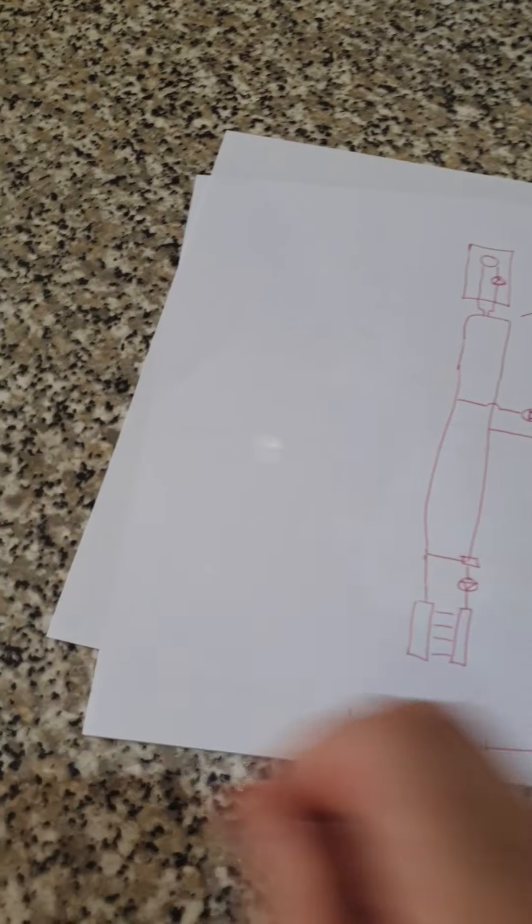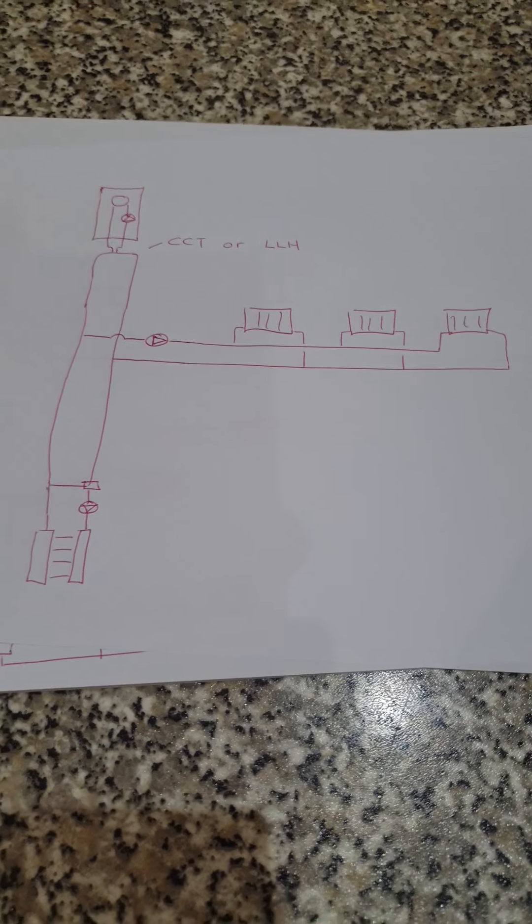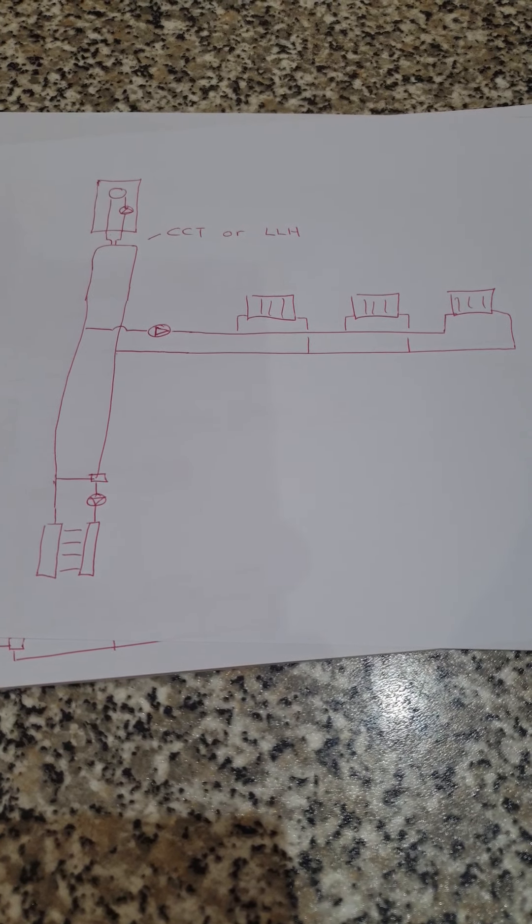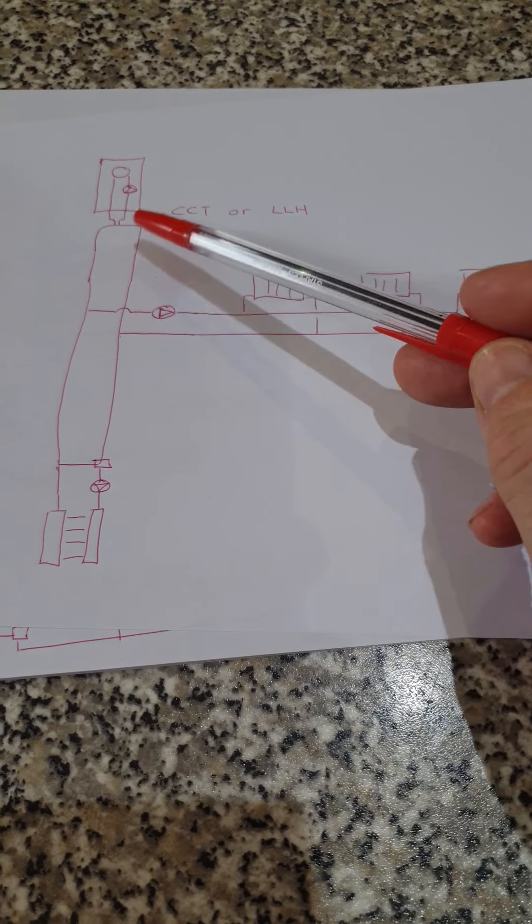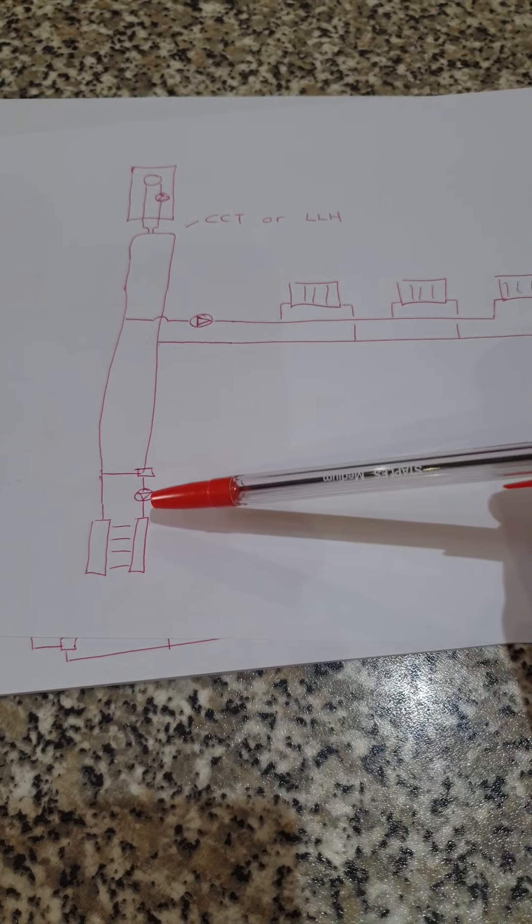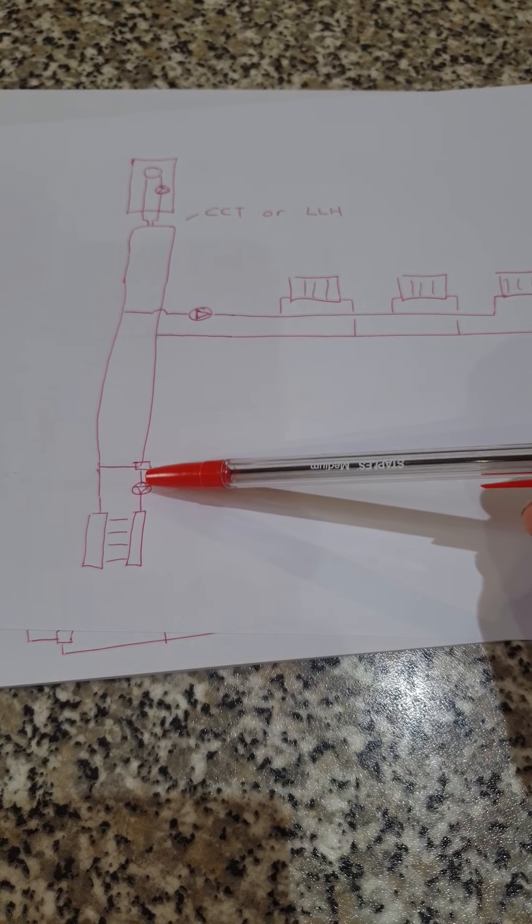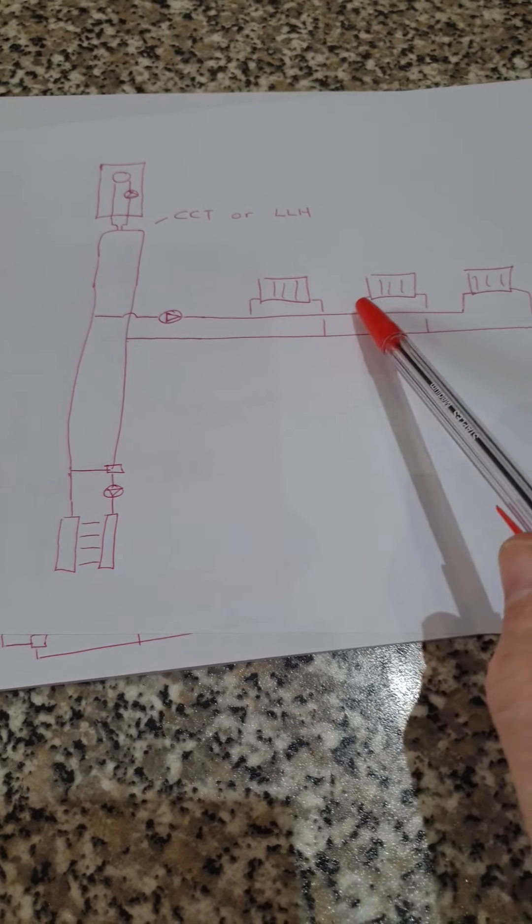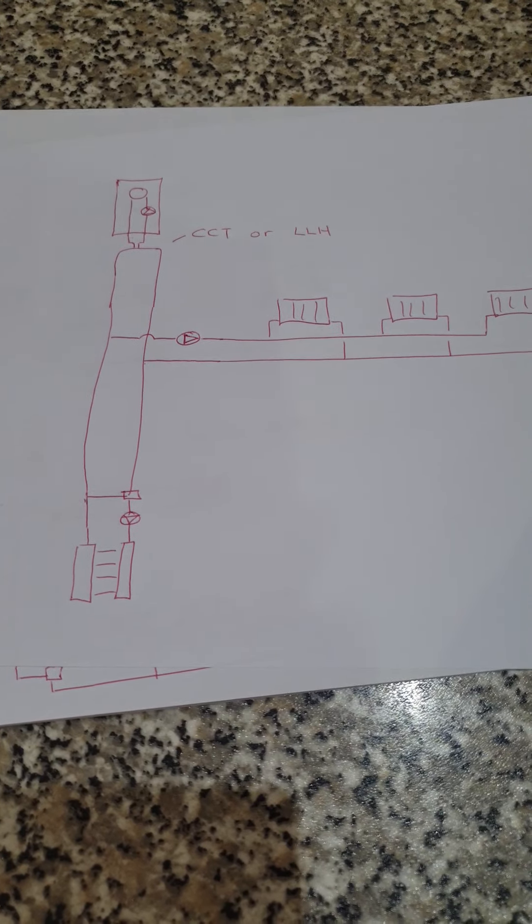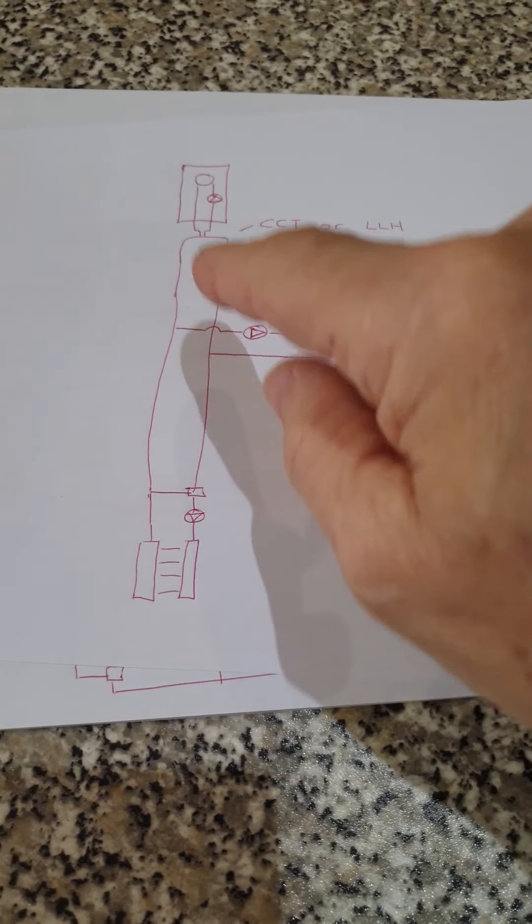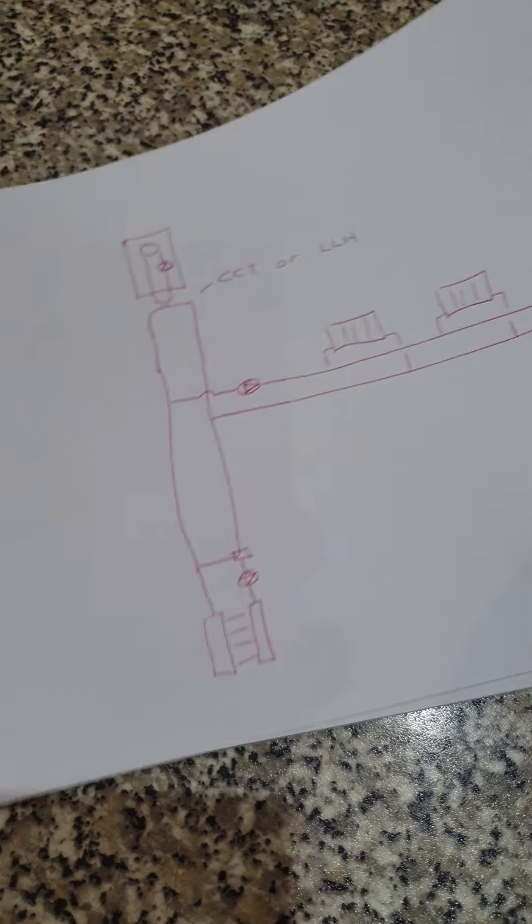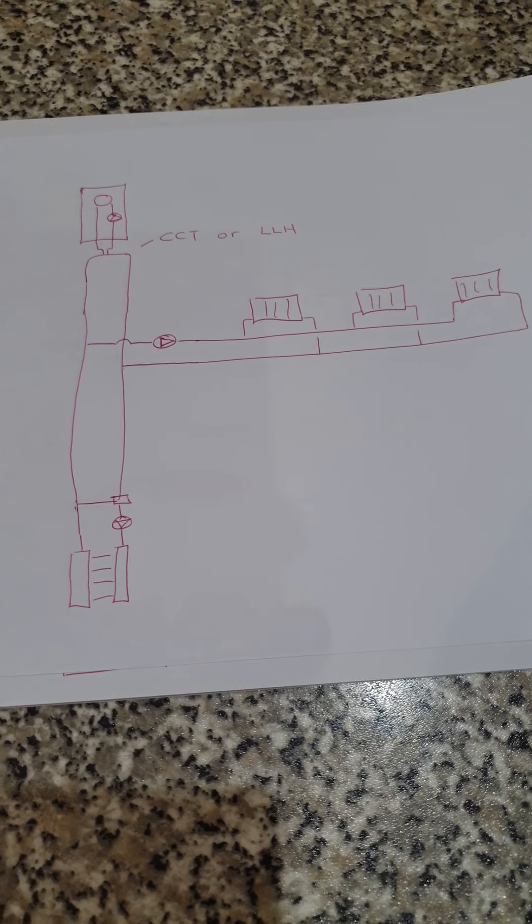This is sort of a standard method that's been used and the one people are trying to work around, which is the use of either close coupled tees or a low loss header at the boiler. And then the heating system, the underfloor heating system, would either use its own pump to draw in or might need to be pressurized. And the radiators should have a separate pump to run the radiator circuit. There's obviously some issues with pipe sizing and stuff here but this is just diagrammatic. So, this is obviously the tried and tested method of doing this.